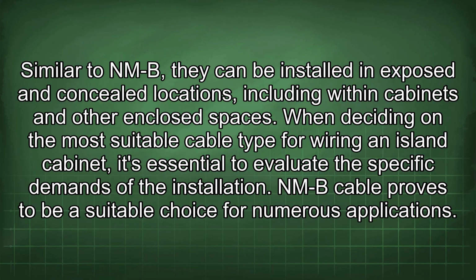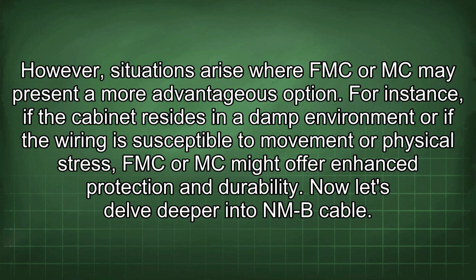When deciding on the most suitable cable type for wiring an island cabinet, it's essential to evaluate the specific demands of the installation. NMB cable proves to be a suitable choice for numerous applications. However, situations arise where FMC or MC may present a more advantageous option. For instance, if the cabinet resides in a damp environment or if the wiring is susceptible to movement or physical stress, FMC or MC might offer enhanced protection and durability. Now let's delve deeper into NMB cable.